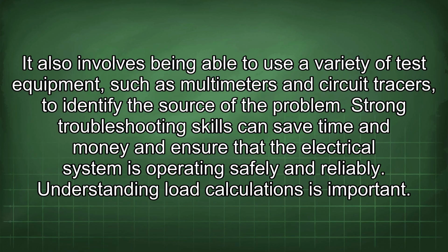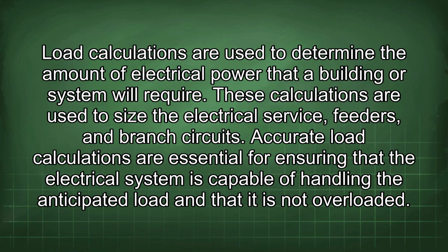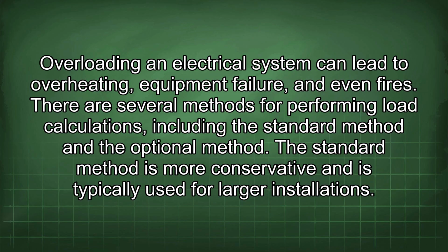Understanding load calculations is important. Load calculations are used to determine the amount of electrical power that a building or system will require. These calculations are used to size the electrical service, feeders, and branch circuits. Accurate load calculations are essential for ensuring that the electrical system is capable of handling the anticipated load and that it is not overloaded. Overloading an electrical system can lead to overheating, equipment failure, and even fires.